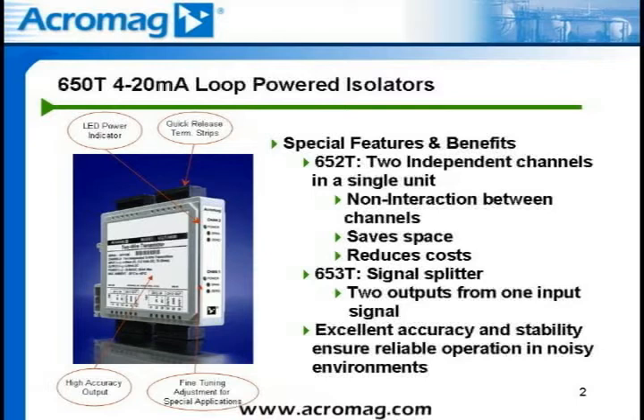These modules realize low temperature drift and wide ambient temperature operation of minus 25 to 70 degrees C, which provides excellent accuracy of better than 0.1% of output span and stability, ensuring reliable operation in noisy environments. Other special features include quick-release terminal blocks for easy installation, LED indication for power, operation, and configuration status, and 15-turn potentiometers for fine-tuning adjustments.